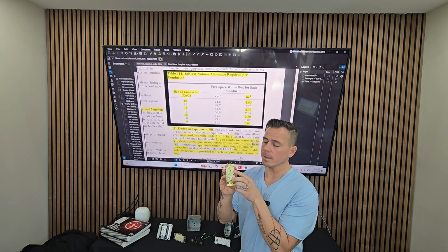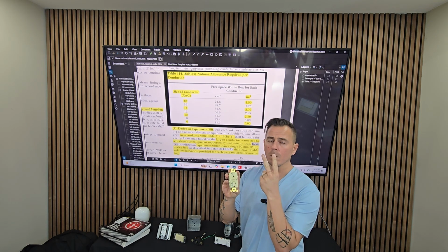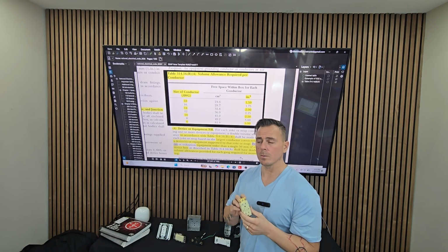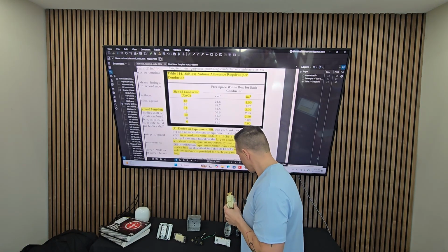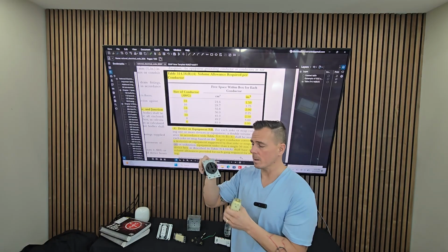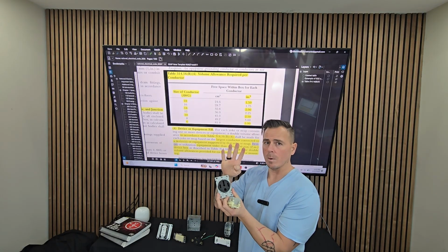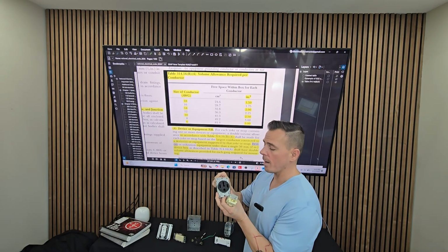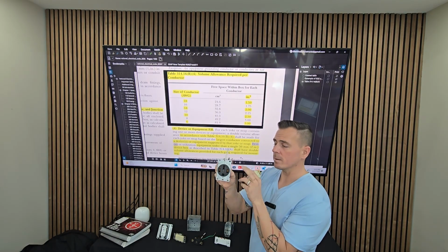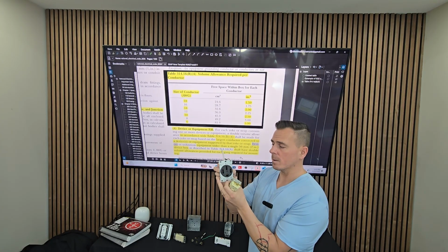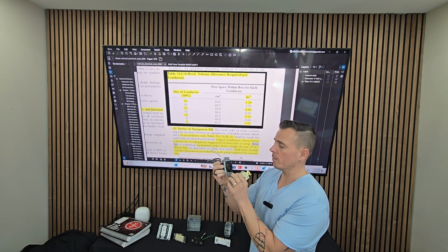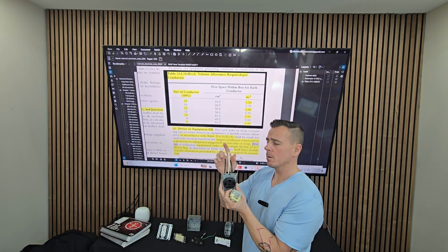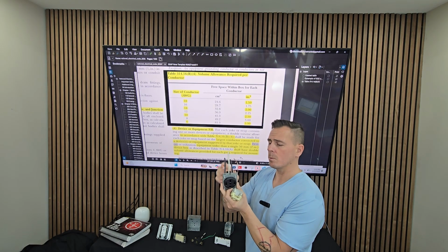If it's a single gang device, it will take 2 extra volumes of the largest wire attached to it. A double gang device, like this one here, would take 4 extra volumes of the largest wire. So say I have number 8s coming onto this 50 amp receptacle here, rated for 75 degrees C, 3 cubic inches of volume, so 3, 6, 9, 12.